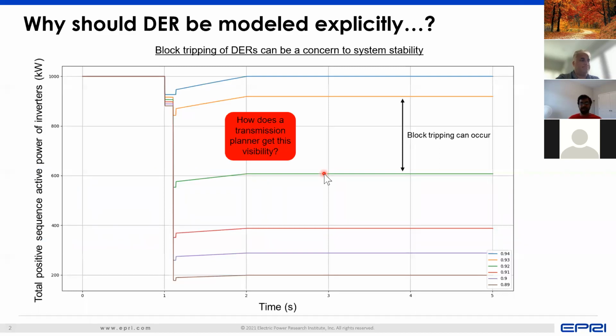So one of the things that we have to set the stage for is, why are we really concerned about this modeling, and what is it about this modeling, or the operation of DER, that we are really worried about? Traditionally, your distribution system network was passive in the sense that it was only load. So the flow of power was from the transmission down to distribution. But now, with distributed energy resources like rooftop PV, both at the individual household level and on something like these big box stores or Walmart or Target, where you might have a lot of rooftop PV, you now start getting a reduction in load at the distribution system end.